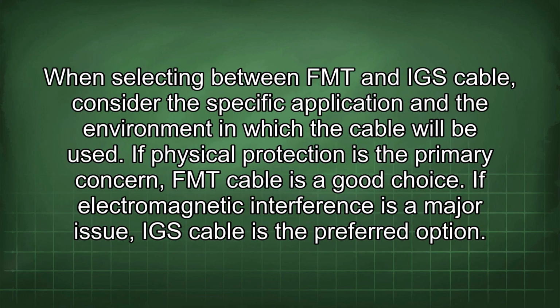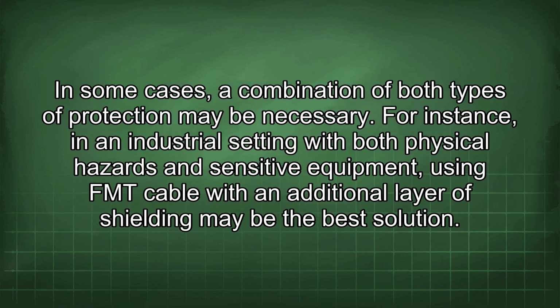When selecting between the FMT and IGS cable, consider the specific application and the environment in which the cable will be used. If physical protection is the primary concern, FMT cable is a good choice. If electromagnetic interference is a major issue, IGS cable is the preferred option. In some cases, a combination of both types of protection may be necessary.